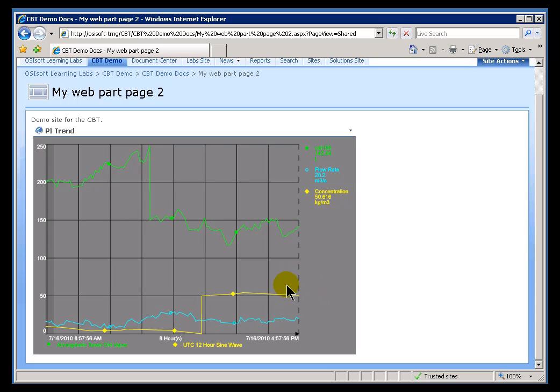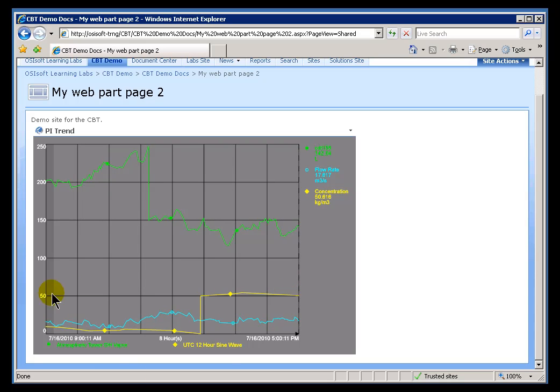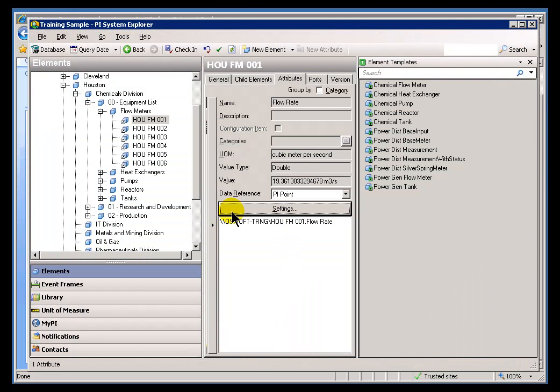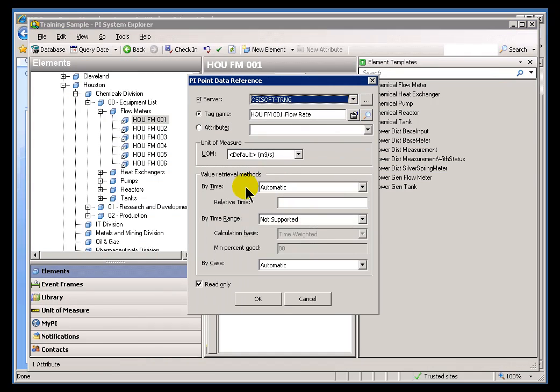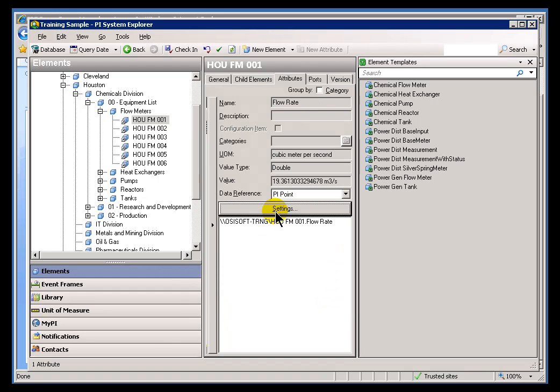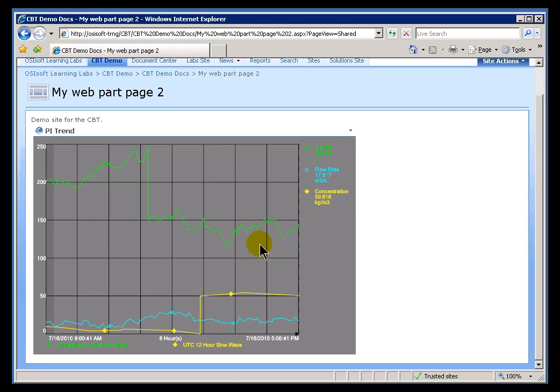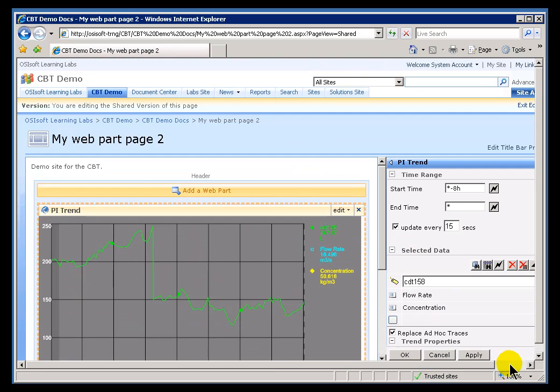You can Trend other things instead of just Data References to PI Tags. If you have a Constant, that's something you can Trend as well. One more thing about the AF Attribute you're going to be referencing here: it has to be a Data Reference to a PI Tag, but it has to be one that hasn't had a modification to the section called Value Retrieval Methods. That's a restriction on what we can currently Trend. If the Value Retrieval Method has been modified, that's something that will not currently be able to be Trended in PI Web Parts.